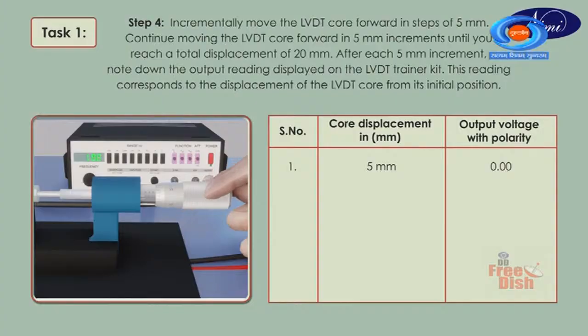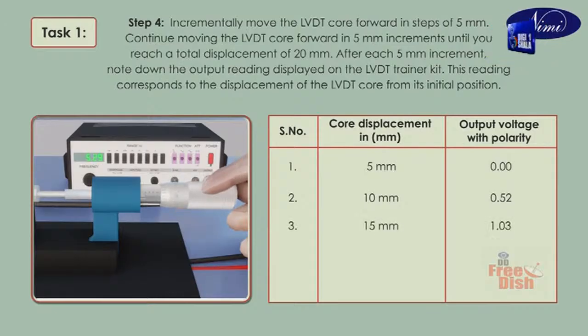Step 4. Incrementally move the LVDT core forward in steps of 5 mm. Continue moving the LVDT core forward in 5 mm increments until you reach a total displacement of 20 mm. After each 5 mm increment, note down the output reading displayed on the LVDT trainer kit. This reading corresponds to the displacement of the LVDT core from its initial position.